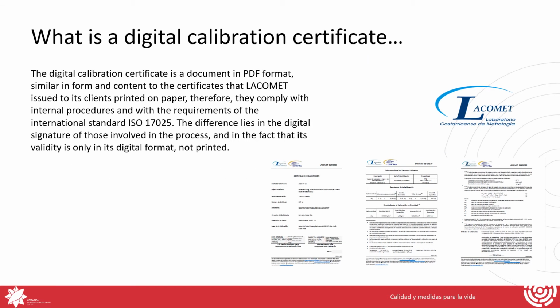But what is the digital calibration certificate? The digital calibration certificate is a document in PDF format, similar in form and content to the certificates that LACOMET issued to its clients printed on paper. Therefore, they comply with the internal procedures and with the requirements of the international standard ISO 17025. The difference lies in the digital signature of those involved in the process and in the fact that its validity is only in its digital format, not printed.